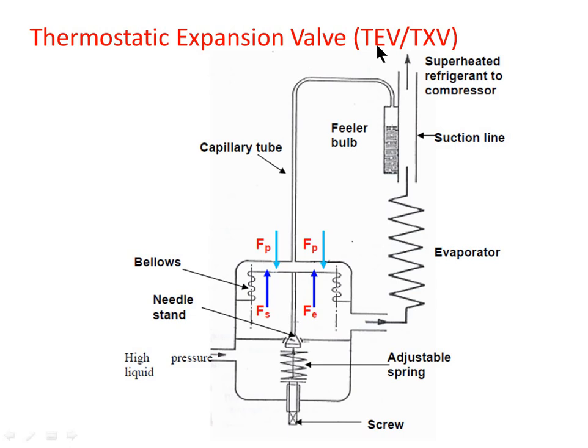Next is the thermostatic expansion valve (TEV or TXV). Despite its name, it is not a temperature control device and cannot be adjusted to vary evaporator temperature. It is actually a throttling device that automatically maintains proper liquid flow according to the load on the evaporator. Its operation is based on the principle of maintaining a constant degree of superheat at the evaporator exit. This ensures the evaporator is completely filled with refrigerant regardless of load, and no liquid spills over to the suction line. Because of its adaptability to load changes, it is mainly suitable for variable load systems.